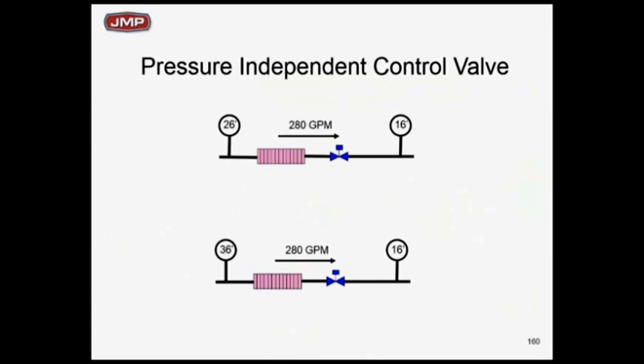I can get the higher delta T. I can get my return chill water temperatures up. I can get my return hot water temperatures down. Yeah, you want to do two separate things there, but it's the same thing. You want the highest delta Ts you can get. In order to get them, pressure-independent control valves will do it for you.